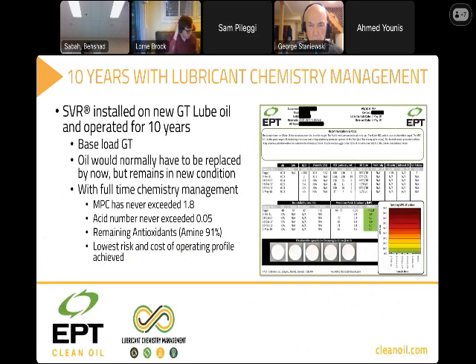So just a couple case studies, and Andrew's presentation is actually a case study, but on the gas turbine lube oil side, I want to show you what is possible. Here's a 10-year case study, lubricant chemistry management. In a lube oil application, lube oils are generally lasting 6 to 8 years. Then they're replaced and flushed quite often. But this is after 10 years base load. MPC has never gone above 1.8, which is better than new. And after 10 years, the primary antioxidant is still at 91% remaining. So that's less than 1% a year consumption rate.